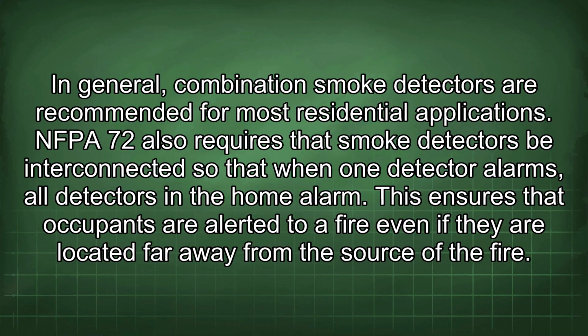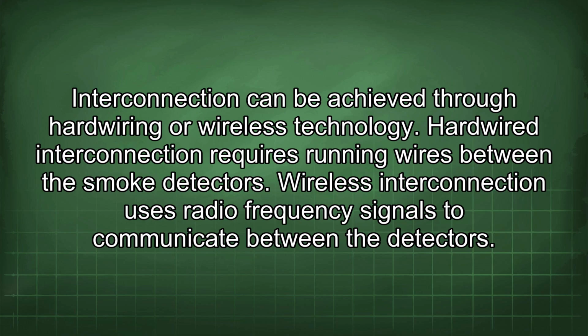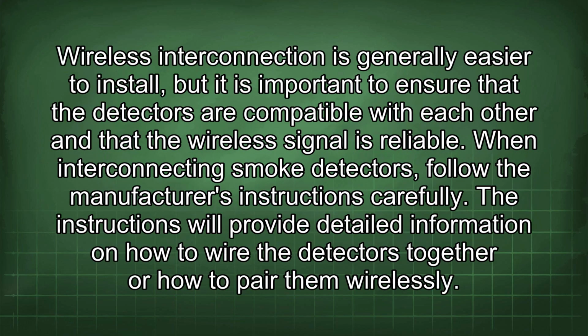NFPA 72 also requires that smoke detectors be interconnected so that when one detector alarms, all detectors in the home alarm. This ensures that occupants are alerted to a fire even if they are located far away from the source of the fire. Interconnection can be achieved through hardwiring or wireless technology. Hardwired interconnection requires running wires between the smoke detectors. Wireless interconnection uses radio frequency signals to communicate between the detectors. Wireless interconnection is generally easier to install, but it is important to ensure that the detectors are compatible with each other and that the wireless signal is reliable.